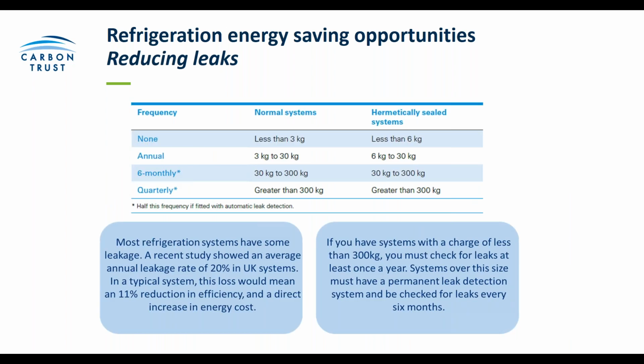Reducing leaks is really important. It's actually part of the regulation obligations that you, as an operator of a refrigeration system, must adhere to, as well as your maintenance service provider. In the UK there's an average leakage rate on refrigeration systems of about 20%, which means that in a typical system you'll see an 11% reduction in efficiency. So while it's a regulation and you need to keep track of the leaks and maintenance, it's actually a benefit to your business to keep on top of these checks, and you can really see energy efficiency gains from doing so. Have a look at this chart and make sure the size of your system is getting the frequency of checks that it needs. If you're in any doubt, there's lots of information on the .gov website about regulation for refrigeration.